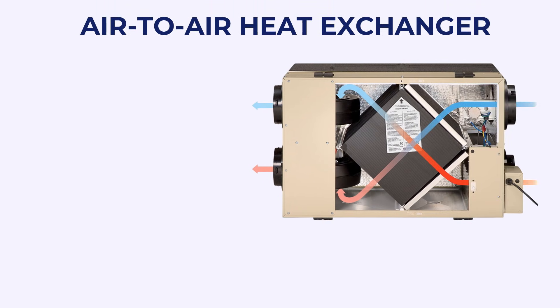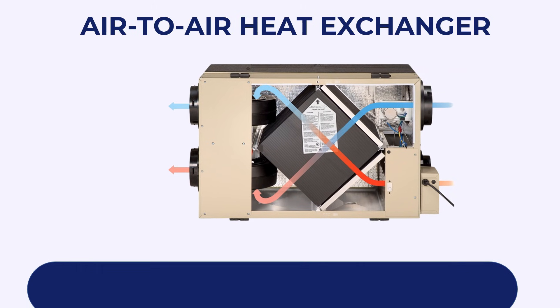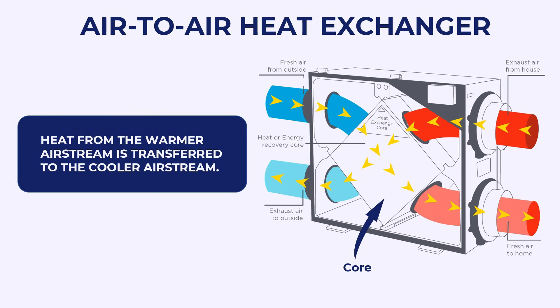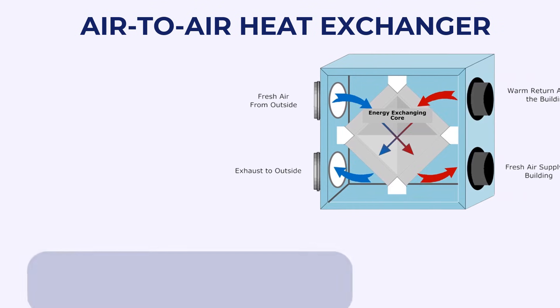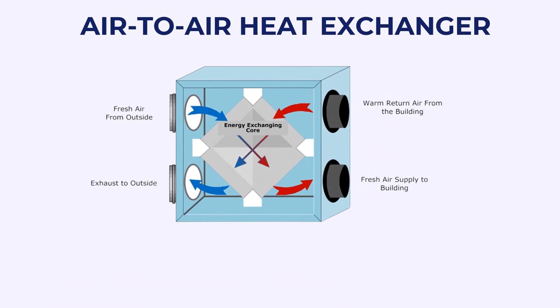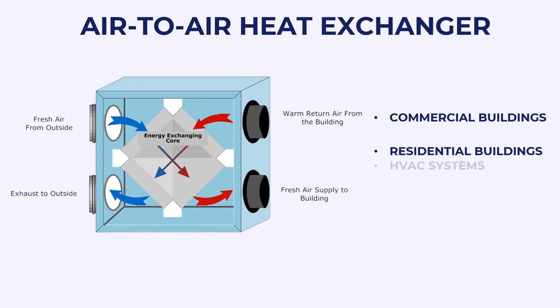Air-to-Air Heat Exchanger. An air-to-air heat exchanger, also known as a Heat Recovery Ventilator (HRV) or Energy Recovery Ventilator (ERV), is a device designed to transfer heat energy from one airstream to another within a confined space. As the air passes through the heat exchanger core, heat from the warmer airstream is transferred to the cooler airstream. By recovering heat energy from the exhaust air, air-to-air heat exchangers reduce the load on heating and cooling systems, leading to lower energy bills. They are mostly used in commercial buildings, residential buildings, and HVAC systems.